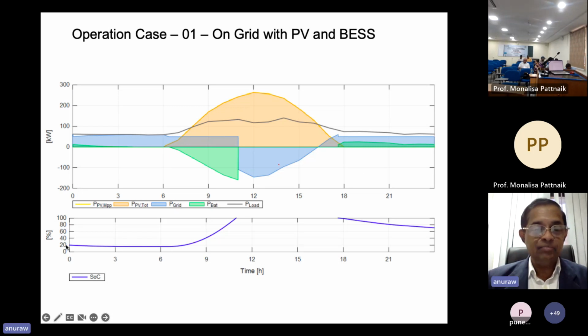Here are the SOC levels. We discharged the batteries down to 20% on this particular day. You can see it charging during the morning hours until about 11 a.m., by which point it's fully charged and kept charged, then starts discharging at about 6 p.m. rather than immediately. So we used a little bit of grid and mainly solar PV to meet the demand that day.